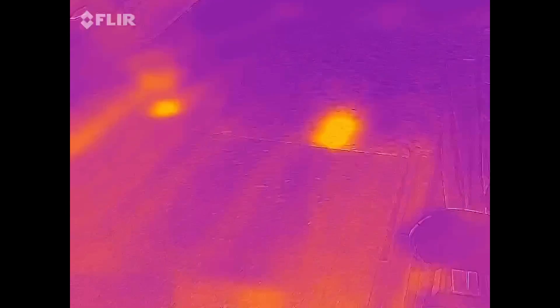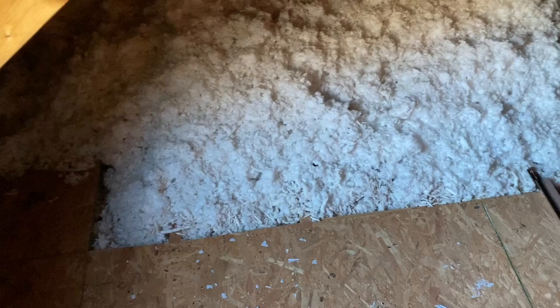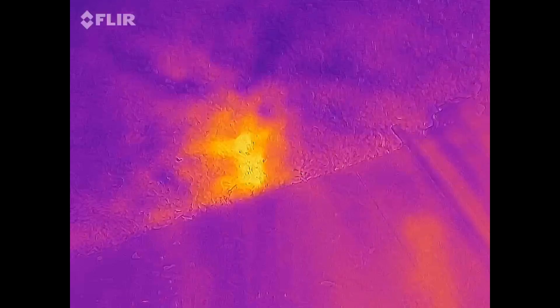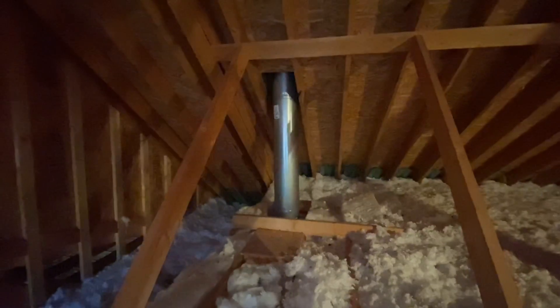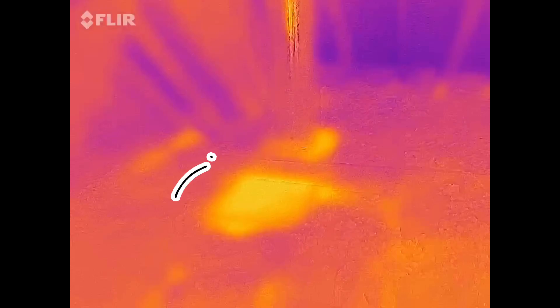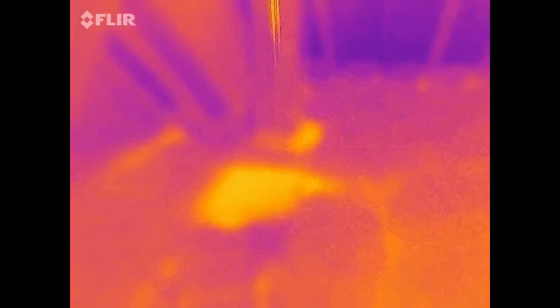This is a radon reduction system here — the really hot part — and there are all kinds of hot spots in the floor I'm seeing. And this is cool: these are the recessed lights I have in the kitchen. You can see that. There's a lot of heat coming through where those can lights are — probably 20 inches deep insulation around them, but still a lot of heat, and it's LED bulbs in those so those aren't hot. They're just a void. Here's where the chimney comes through — we saw how cold the chase was in the living room — and I see a lot of heat getting out the top of that chase. There's no insulation over the top of the box.